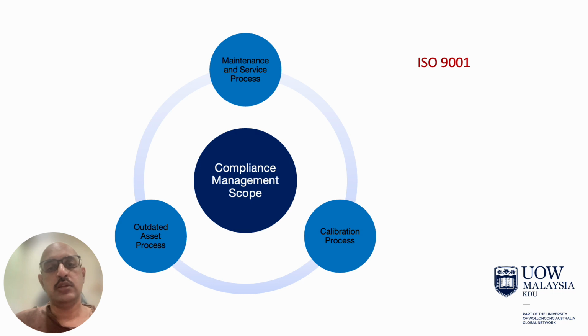Whereas the calibration process is considered like a major service, whereby service personnel will drop by the site or take the equipment back to their place to conduct proper calibration, ensuring a period of time before the next major service. They will then give a certificate-like document stating that this equipment is compliant and safe to be used during that period.